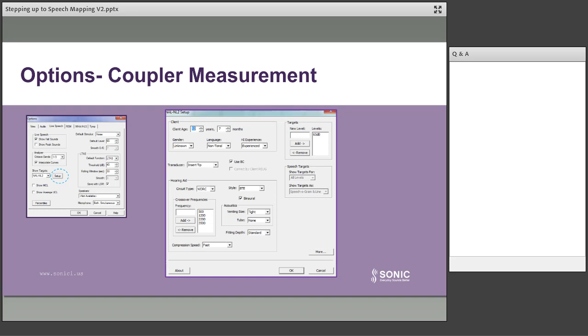Now, there are a lot of parameters there, and for coupler boxes, the most important ones are these ones down the bottom. So we know that if you have a BTE with a thin tube versus a BTE with a standard 13 tubing, the output of the hearing aid at the end of the tube is different. We know that high frequencies don't travel down those thin tubes as well, and so we really do need in this section to say what sort of tubing we're using along the way.